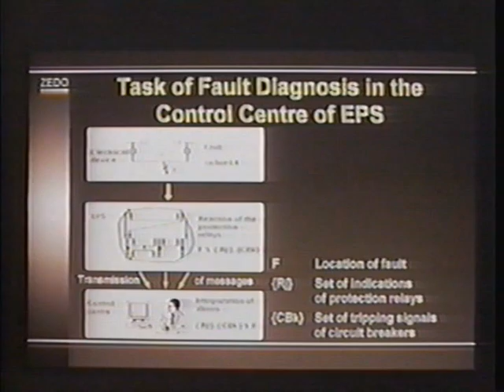So the protection relays installed at a certain line, for example, generate messages and alarms, and these may be sent to a central control center where the operator of the electrical power system has to draw the conclusion where the location of the fault can be. That is most simple if at the beginning and at the end of the line the protection relays detect a fault on the line. They generate messages, and the operator has just to draw the conclusion that the fault is in between both protection relays.